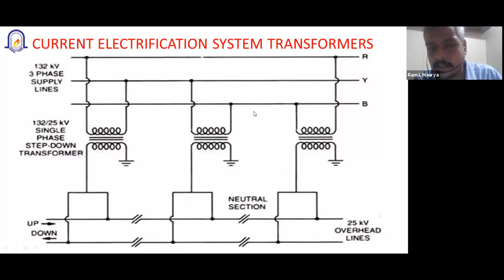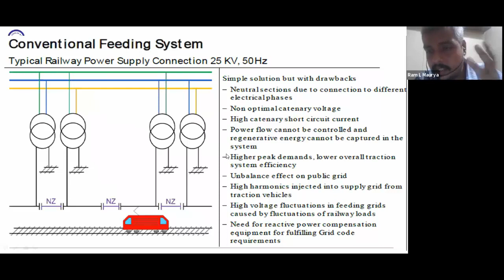You will have noticed that when you are going out, approximately between Andheri, all the lights of the train go off and only the central lights remain. Such things happen because of the neutral section. So these neutral sections are there, and there is unbalance in the grid in this conventional system. Also, power control is not available to you.